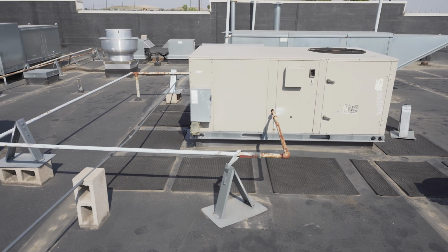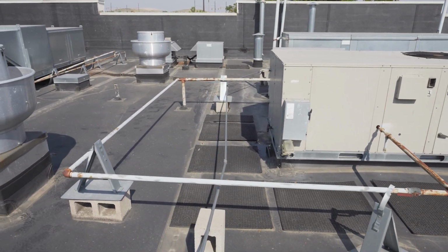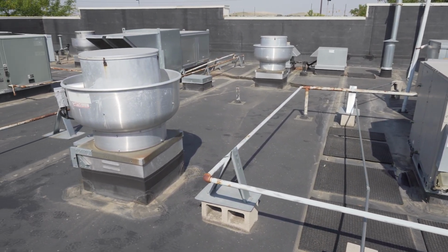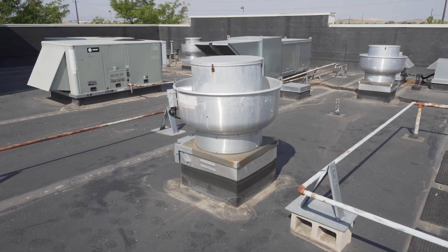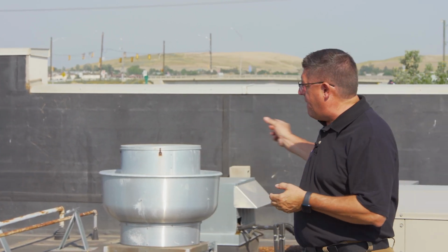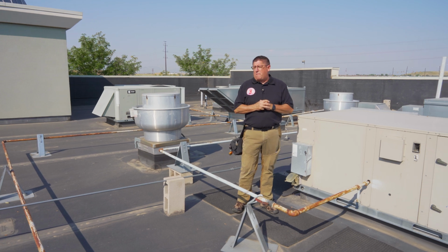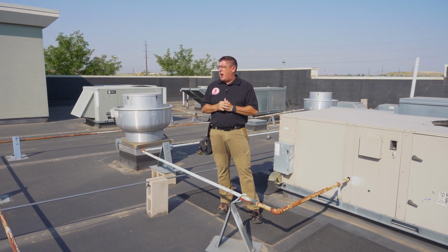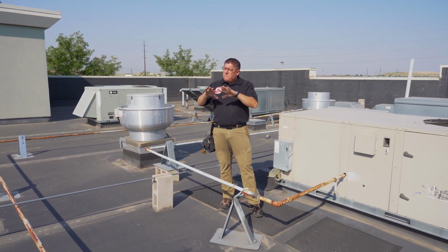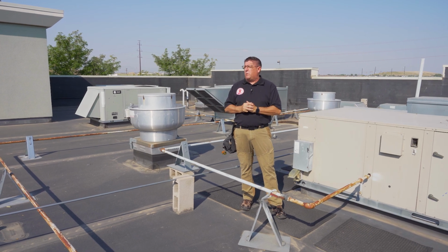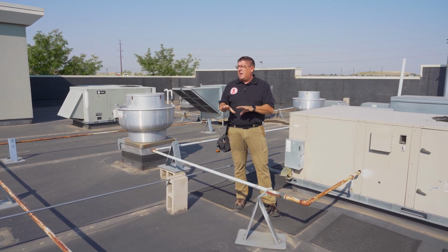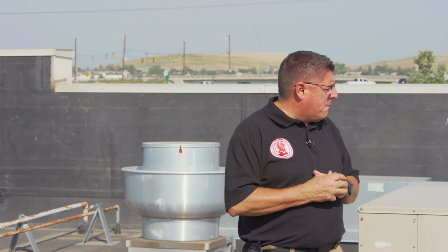When we look at our gas pipe, you'll see at one point this was wonderfully painted. Now it's lost its coloring. Again, to re-emphasize, the coloring is so important: it should be painted yellow or labeled gas in yellow tape with black writing on it, and that should be every 5 feet. You'll see that the gas pipes up on this roof are up on chairs. The chairs are preventing it from laying on the roof and abrading the roof, as well as abrading the pipe itself. So we want to double check for that.